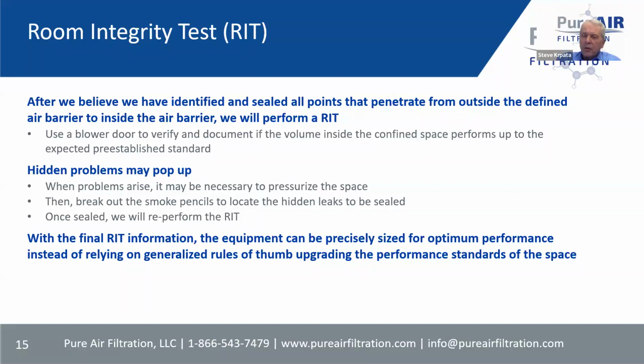You're not going to have it perfectly hermetically sealed. There's always some air flow in there, and it's not unusual, for example, for a sealed room to have 2 to 3 air changes an hour based on the normal airflows that will get into the space. And if it gets to that point, then that's pretty good, and we can say job well done.